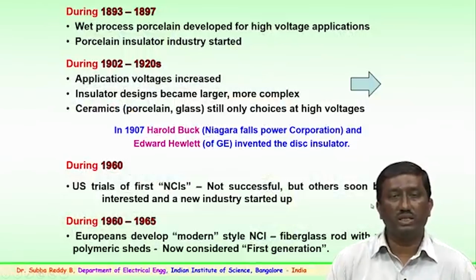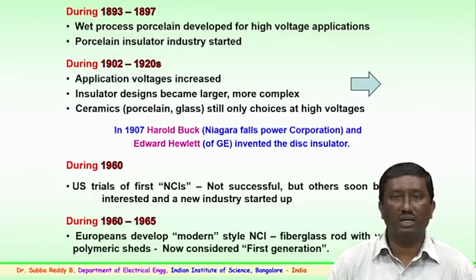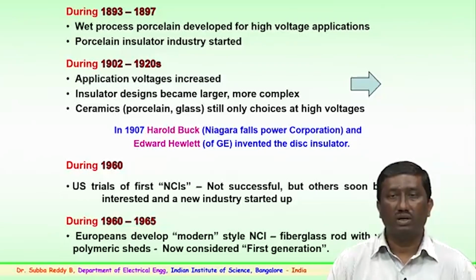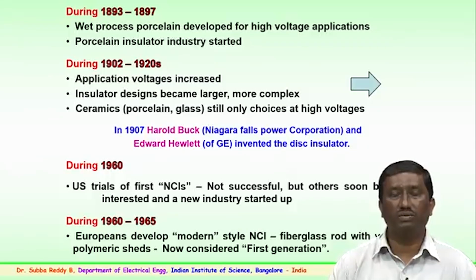So, during the 1960s the first non-ceramic insulators, that is polymer, silicone rubber, composite, what we call, trials started in the 1960s, but they were not successful initially because of the problems they were facing. Many companies tried to start, and some companies had to close down, and parallelly the industry was also looking into how to improve the ceramic insulators. During the 1960s to 65 the Europeans developed the modern non-ceramic insulator with fiberglass rod technology, which is considered the first generation.